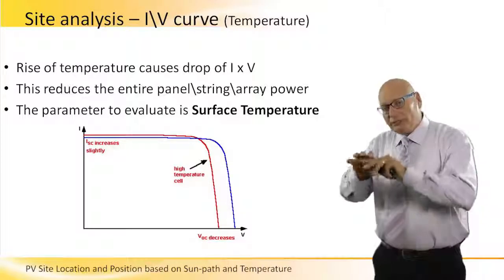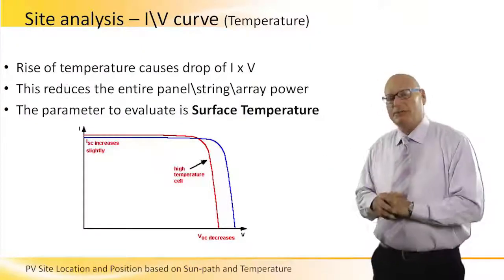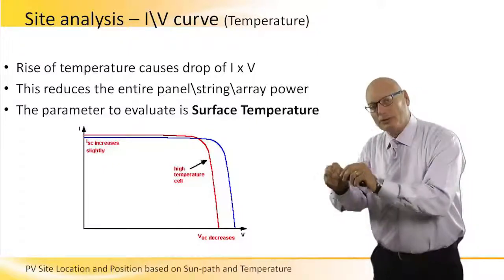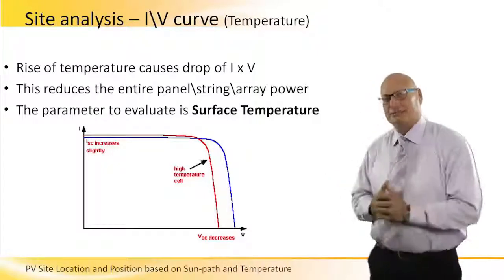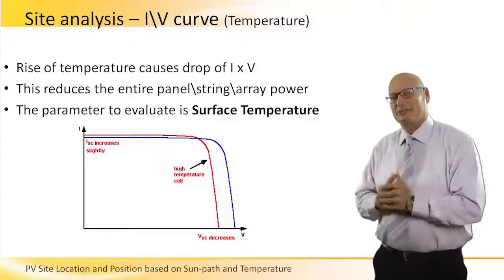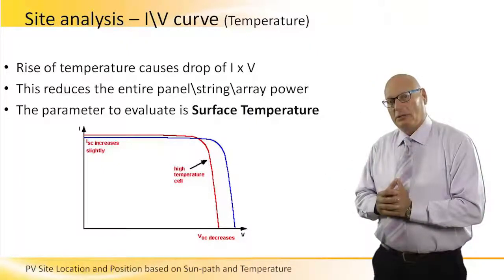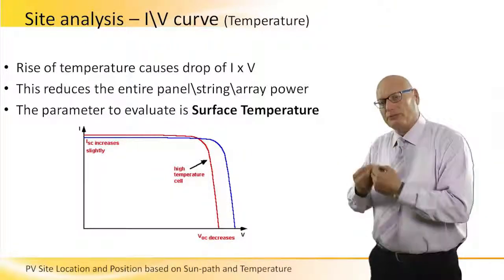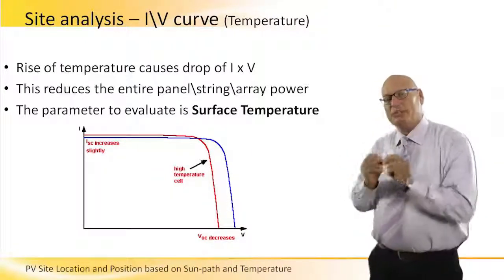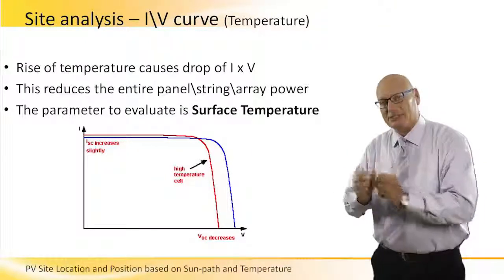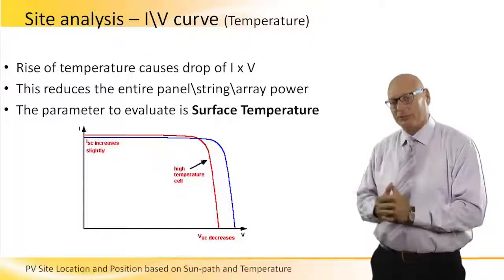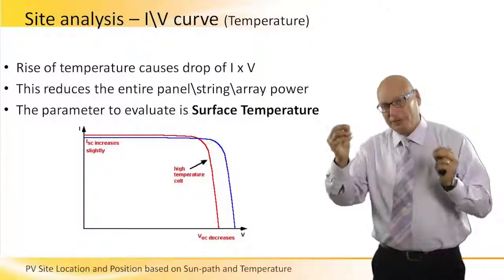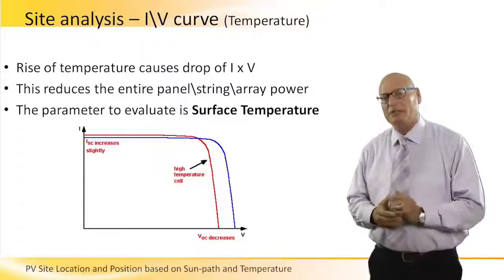These 55 to 60 degrees — this is really what the silicon of the panels experiences. So the efficiency drop due to temperature is based on the surface temperature, not the environmental temperature. This is very, very important. The difference between them is tremendously high.